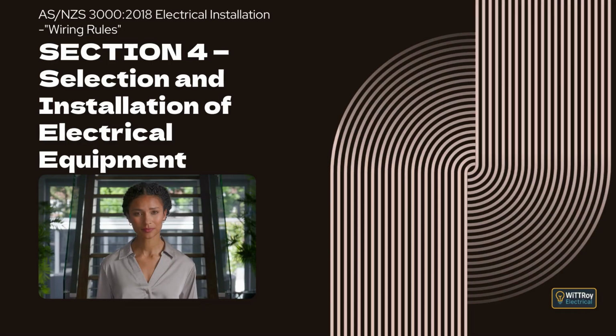Clause 4.3.3, Installation wiring connected by an installation coupler or couplers. This clause introduces requirements for wiring connected using installation couplers. Clause 4.3.3.1, General. This clause explains that cords or cables connected by an installation coupler must be heavy-duty sheathed types suitable for the protective device, adequately protected and installed to reduce mechanical damage, supported and fixed correctly, and kept as short as practicable, with a specific allowance for reduced cable size where wiring terminates within a single item of equipment such as a luminaire or single socket outlet.